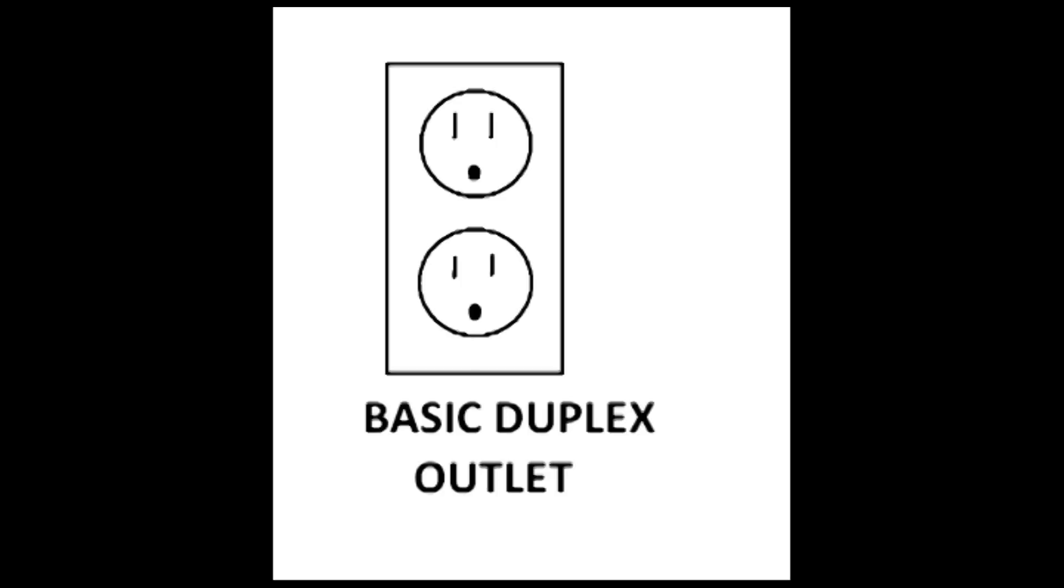Now there are variations to this symbol and all have different meanings, but they're just not used. Instead, these common abbreviations or words are used. WP or weatherproof—that denotes a weatherproof cover goes on that outlet. GFI—that's a GFI protected outlet and is usually found in a bathroom, kitchen, or outside.